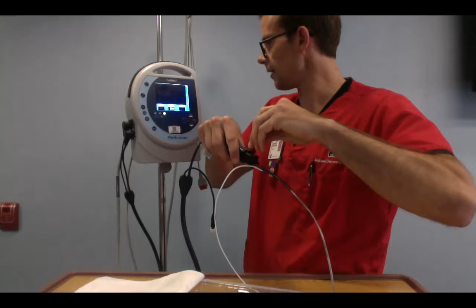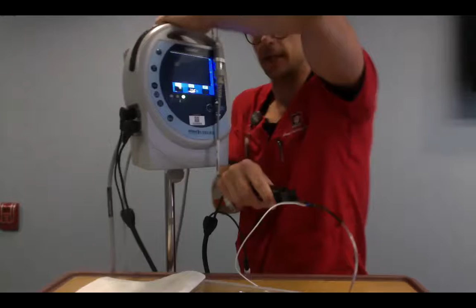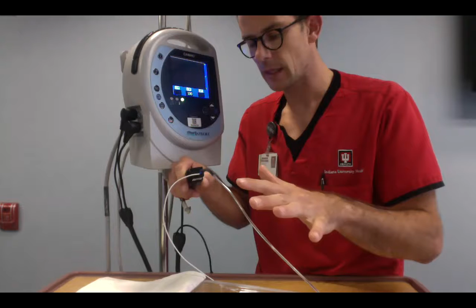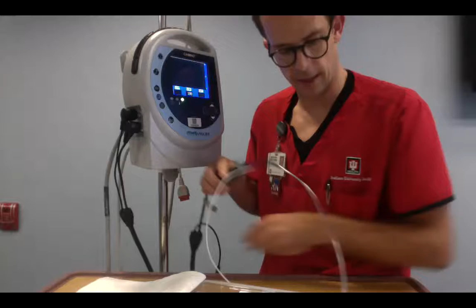Since it's an educational catheter, it's been used and abused, it's not going to read anything. I am dialing it and you can see the ICP number changing, but it's not giving me anything on the graph. So once you have it zeroed, you can wrap a towel around it. You have to be careful because this is close to the sterile field. And this is not sterile, and you've connected a non-sterile thing to a sterile thing. So you have to be really careful with that.